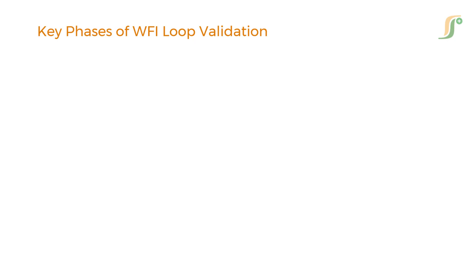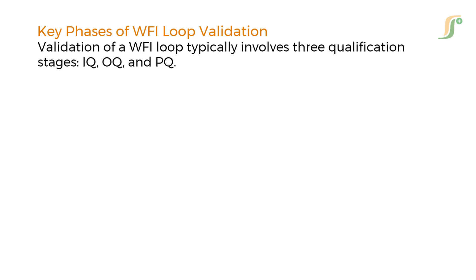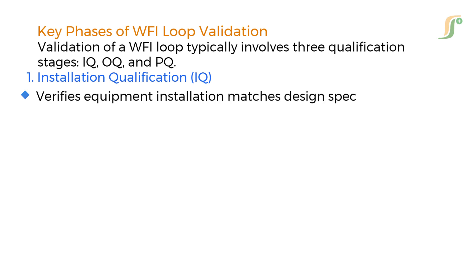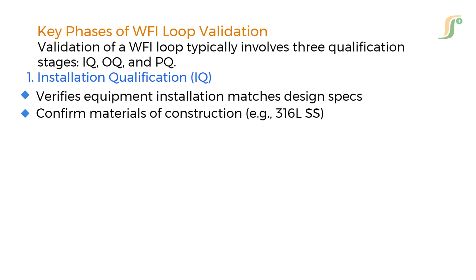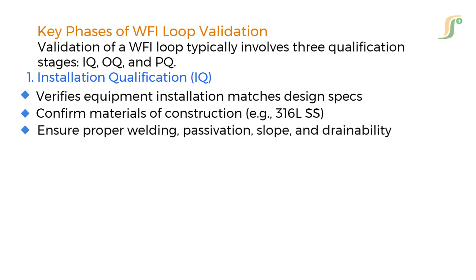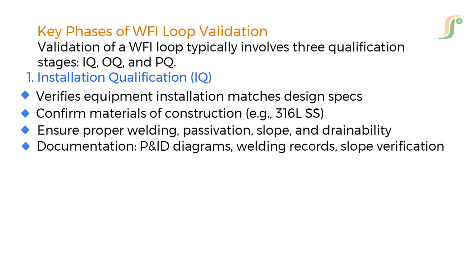Validation of a WFI loop typically involves three qualification stages: IQ, OQ, and PQ. First, Installation Qualification verifies that equipment installation matches design specifications. Confirm materials of construction — 316L stainless steel. Ensure proper welding, passivation, slope, and drainability in tanks and pipes. Documentation, P&ID diagrams, welding records, and slope verification are necessary to complete.